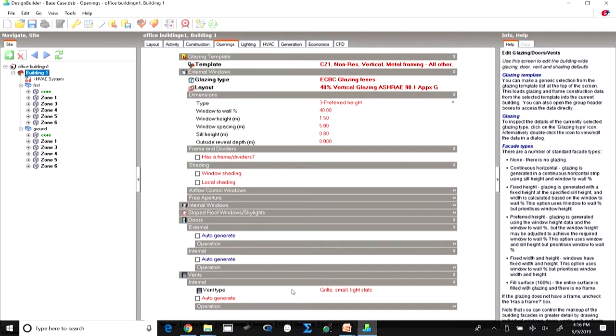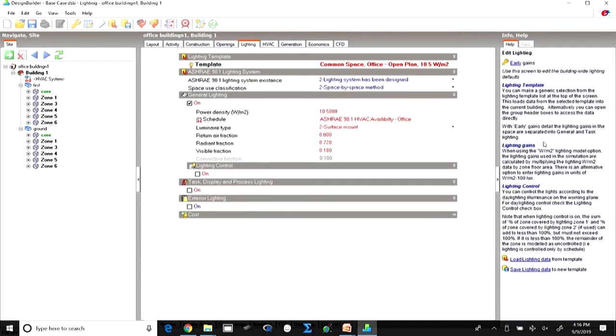Once we have created the building geometry, construction and openings, we move on to the active features. First is lighting. A common space template for an open plan office has been taken, where the lighting power density is 10.5 watts per meter square — which is also taken as the base case value in ECBC. We are taking it as 10.5 W/m² for general lighting.